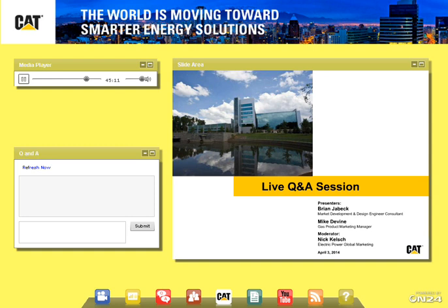You have 50 hours of general use in that 100 hours, which can include storm avoidance. And then you do have 50 hours a year that is allowable for demand response programs. But again, that's out of your 100 hours of maintenance and testing. Those are really the key limitation there, how you choose to run it outside of in the event of an actual utility outage.